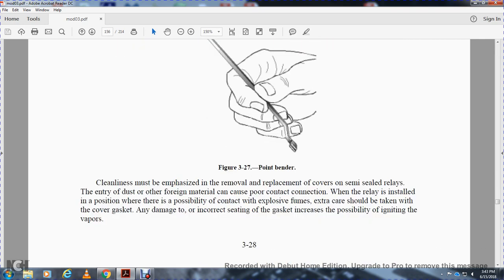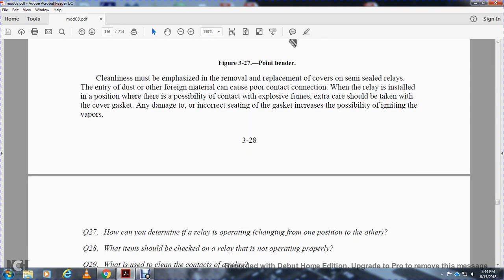Cleanliness must be emphasized during removal and replacement of semi-sealed relays. The entry of dust or other foreign materials can cause poor contact connection. If the relay is installed in a position with the possibility of contact with explosive fumes, extreme care should be taken with the cover gasket. A damaged or incorrectly set gasket increases the possibility of igniting the vapors.